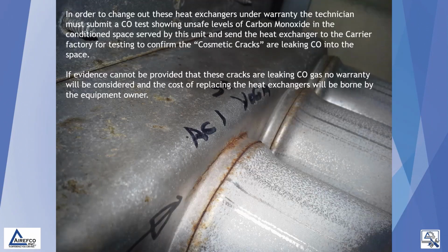In order to change out these heat exchangers under warranty, the technician must submit a CO test showing unsafe levels of carbon monoxide in the conditioned space served by this unit and send the heat exchanger to the Carrier factory for testing to confirm the cosmetic cracks are leaking CO into the space. If evidence cannot be provided that these cracks are leaking CO gas, no warranty will be considered, and the cost of replacing the heat exchangers will be borne by the equipment owner.